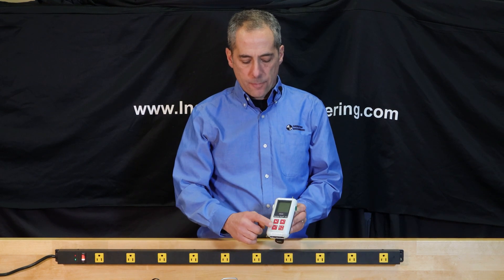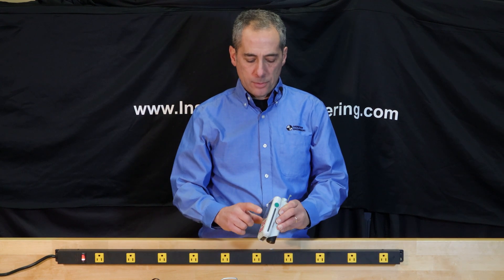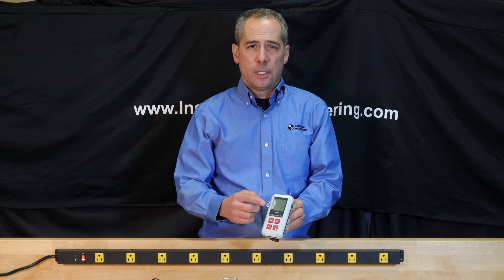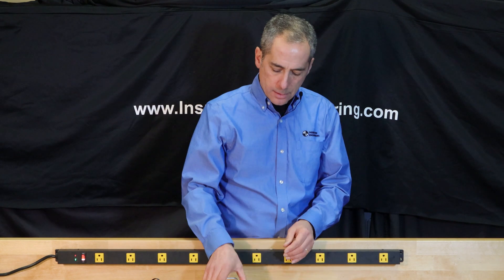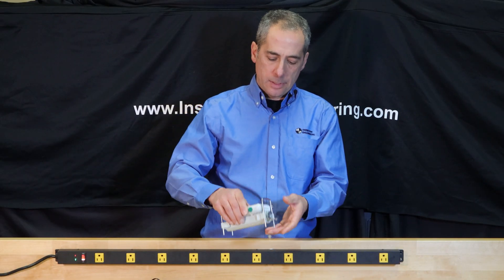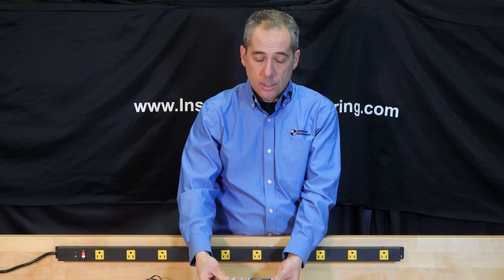The system has four soft keys that are red to control the menus, and green keys on each side that allow users to do commands such as start a trace, power on, and power off. It also comes with a convenient cradle. You can snap the unit right into it and adjust it to the exact height of whatever it is you're measuring.